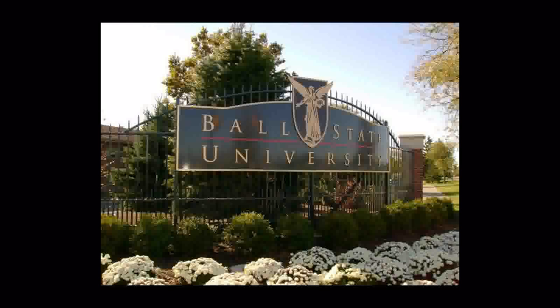I'll take the first question. We actually installed several test wells—installed a real well, did the conductivity testing, had the results provided to the designers as they used their software programs to determine spacing and lineal feet. Those test results were critical in determining how we went about the spacing, the depth, and the conductivity rating.